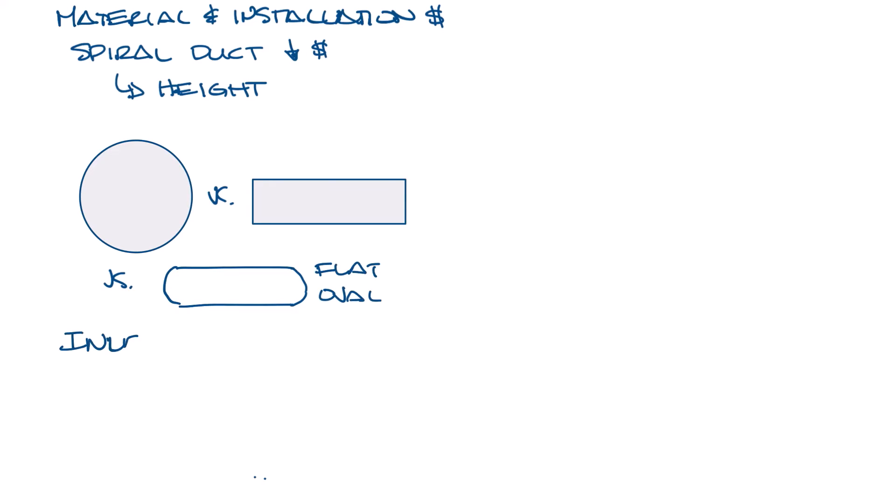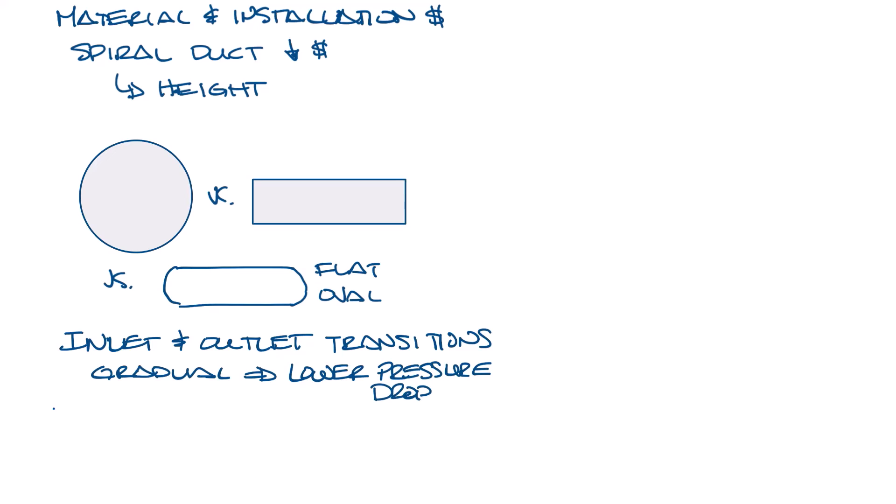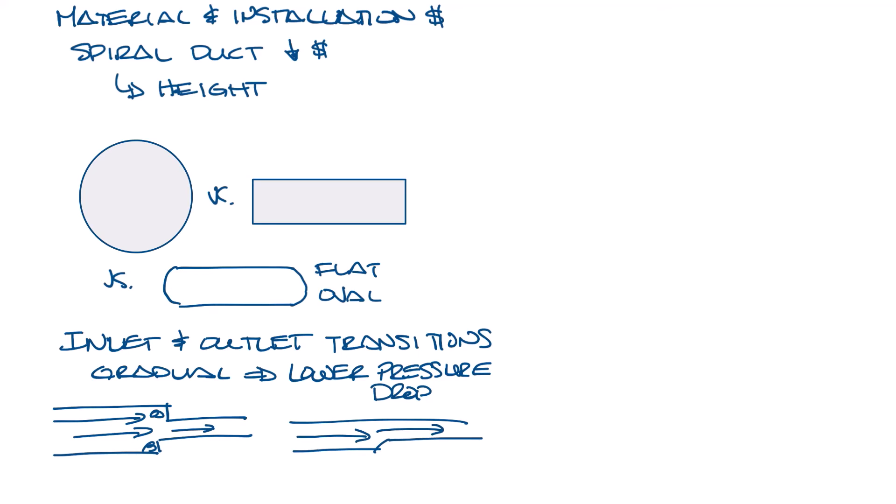Inlet and outlet transitions will affect pressure loss as well. The more gradual the transition, the lower the pressure loss. If you had a transition that looks like this, the airflow would move through it kind of like this, and the sudden change in duct size would cause turbulence at these corners. So this transition has a lower pressure drop than a sudden change in ductwork, and then this transition would even be better.